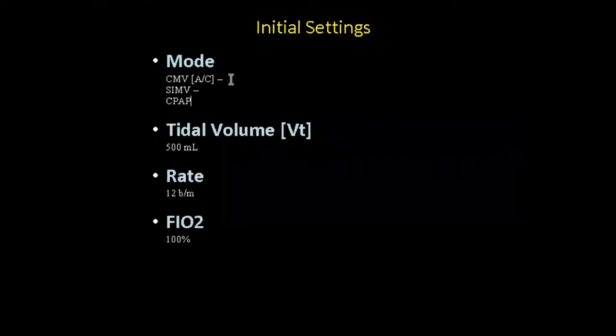The last mode is Continuous Positive Airway Pressure, or CPAP, also known as spontaneous mode — it is completely all spontaneous breathing. This mode is good primarily for weaning. We leave them connected to the ventilator because we can add a little help to their spontaneous breathing with pressure support, plus you get FiO2 delivery and alarms — if they get tired or disconnected, it'll let you know.